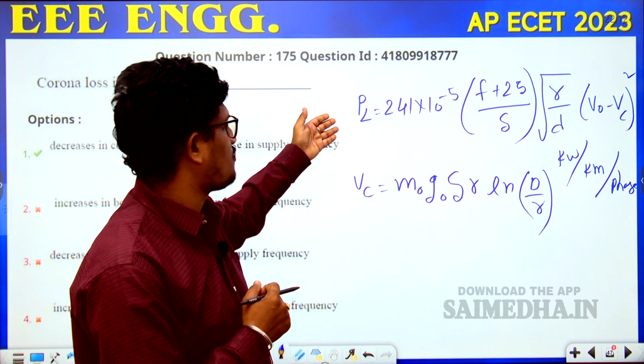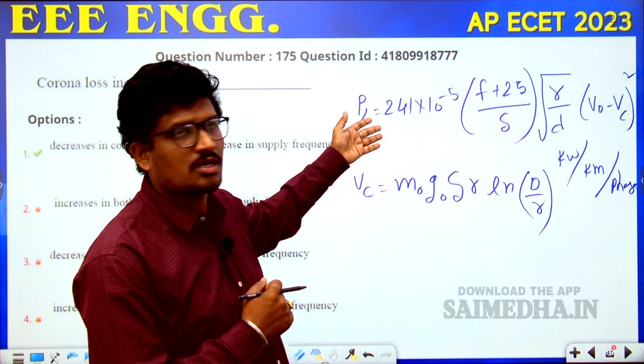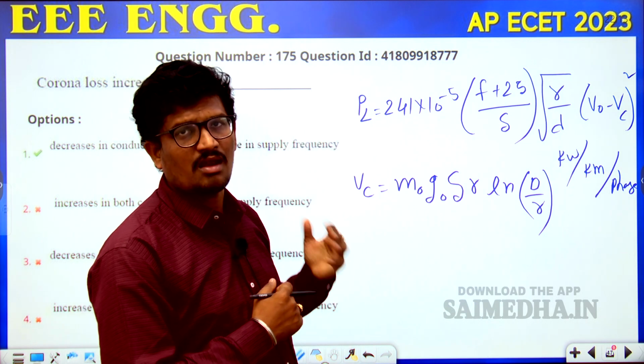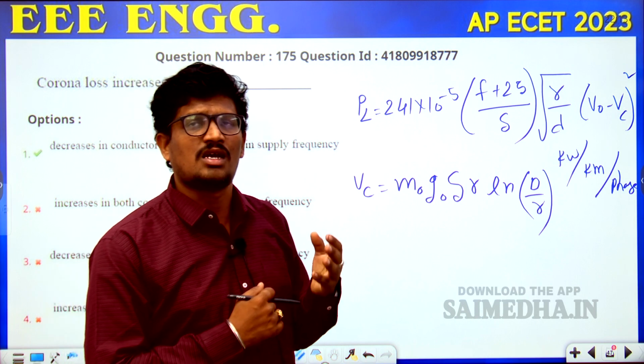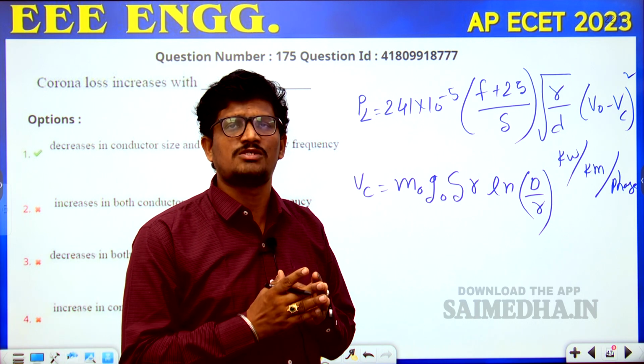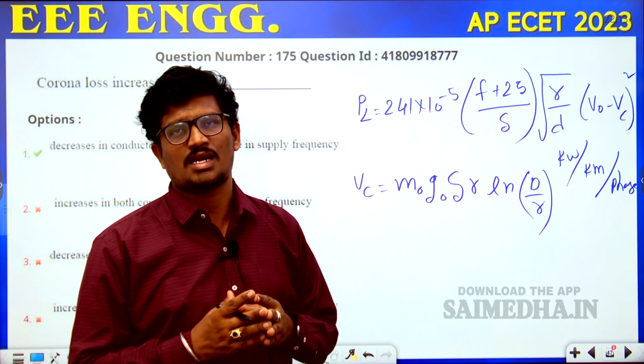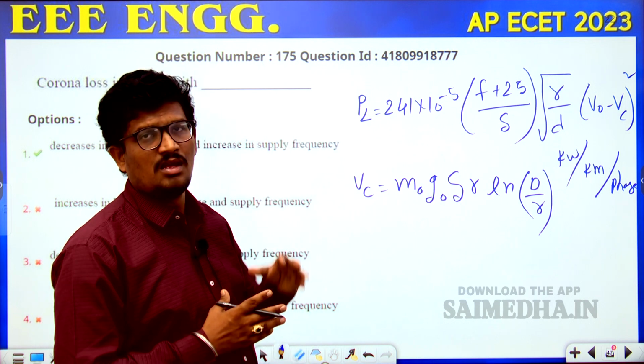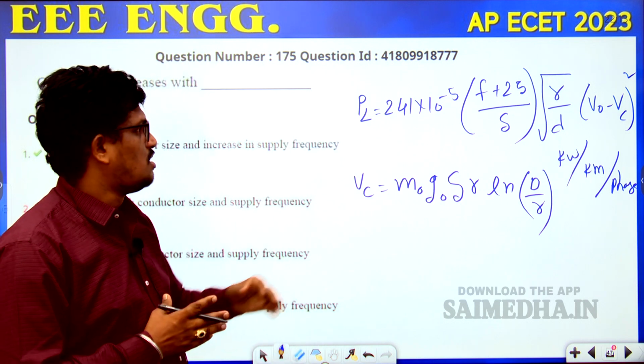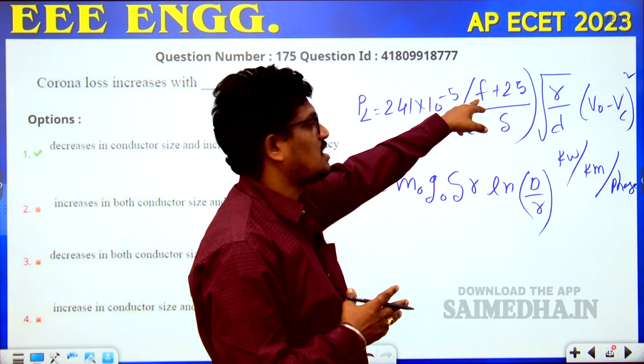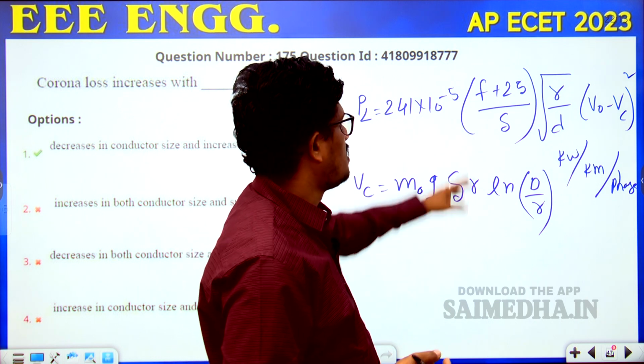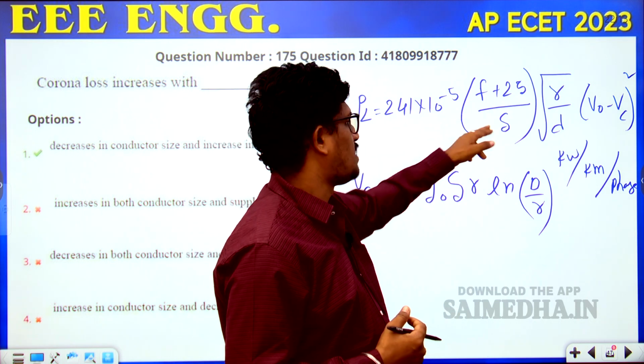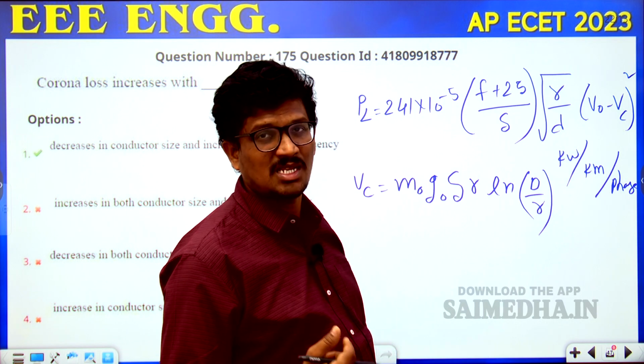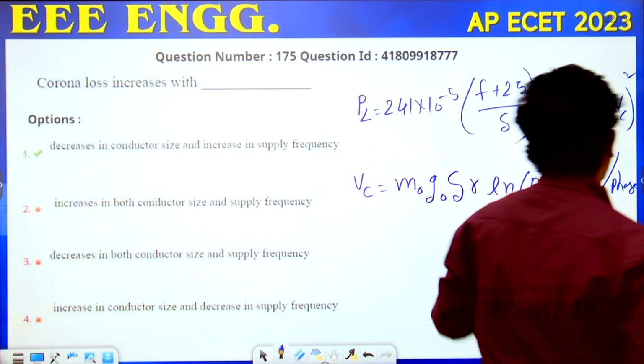Look at this formula—this is for corona losses or power losses. Corona occurring in a transmission line causes a huge amount of power loss. This is the formula for power loss due to corona: 241 times 10 to the power minus 5, times (F plus 25), divided by delta, the air density factor, multiplied by the square root of R by D.